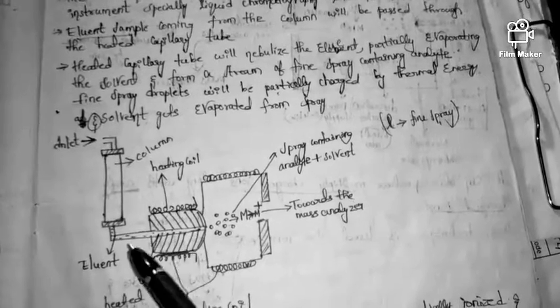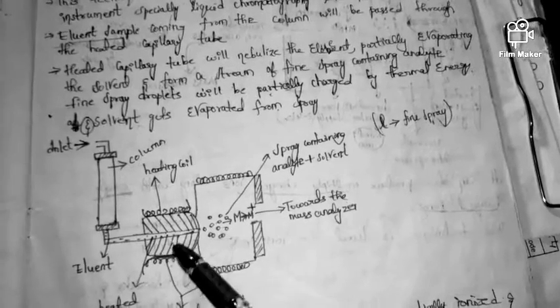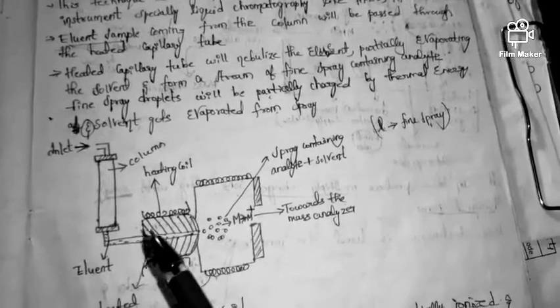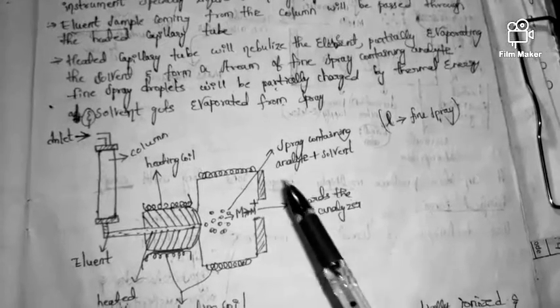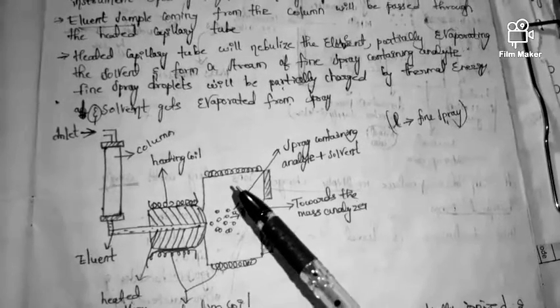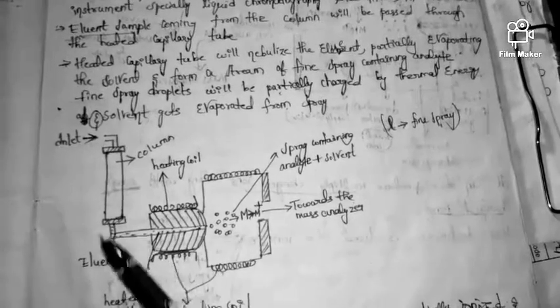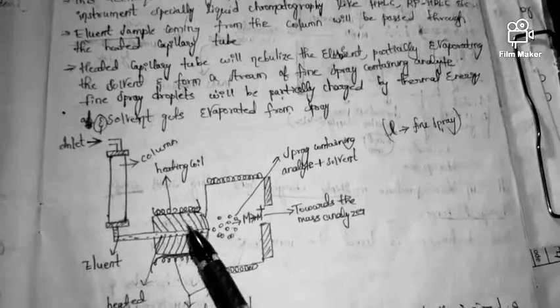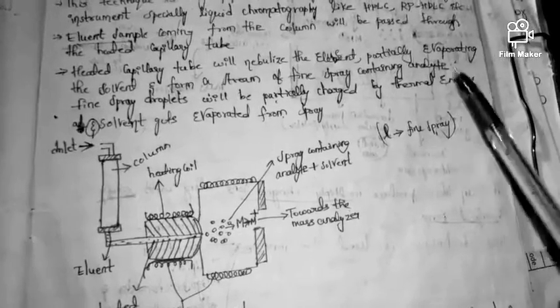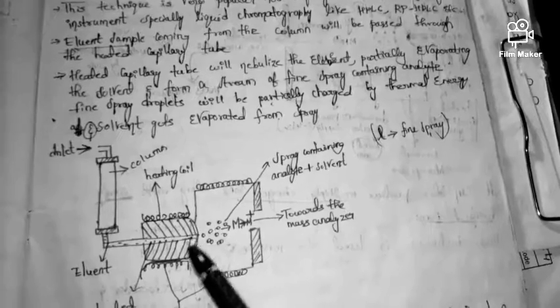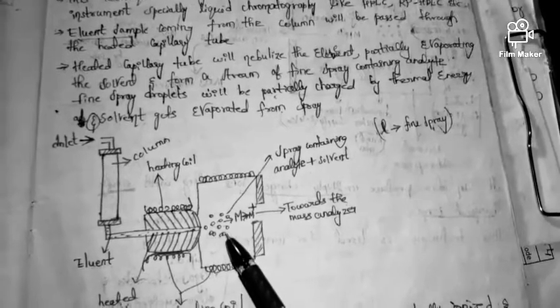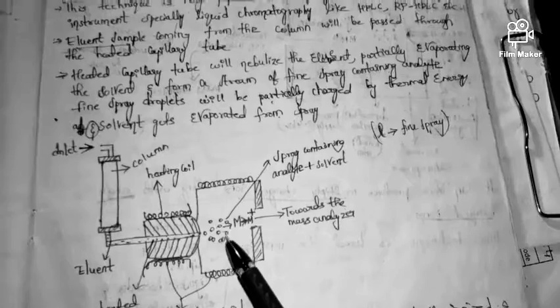The heated capillary tube will nebulize the eluent. Nebulization means the conversion of a liquid into a fine spray. So the eluent from the column is nebulized, partially evaporating the solvent and forming a stream of fine spray droplets.